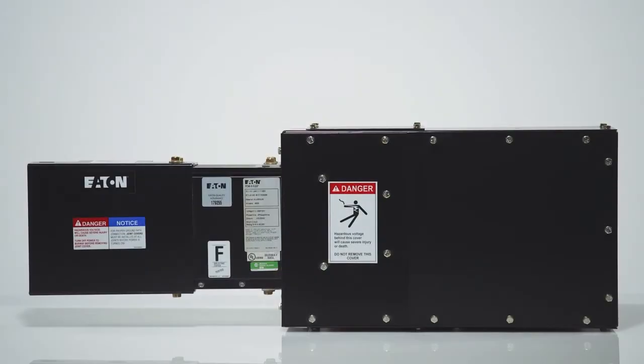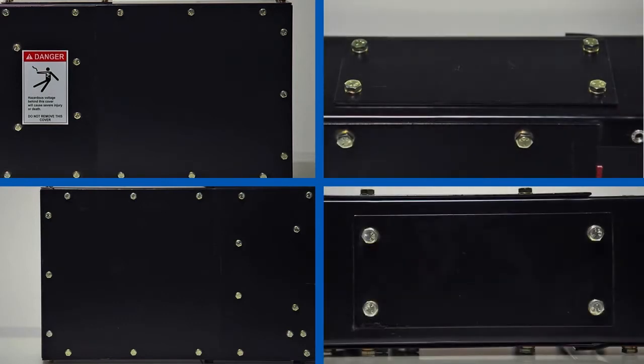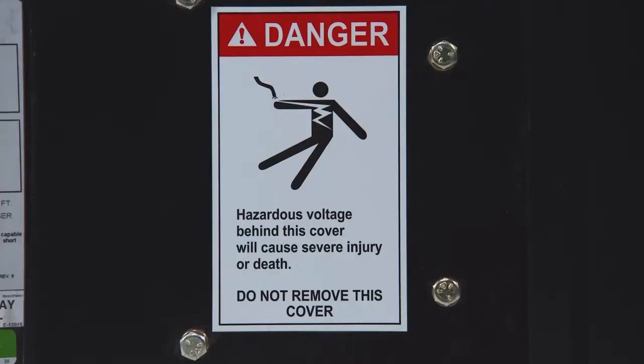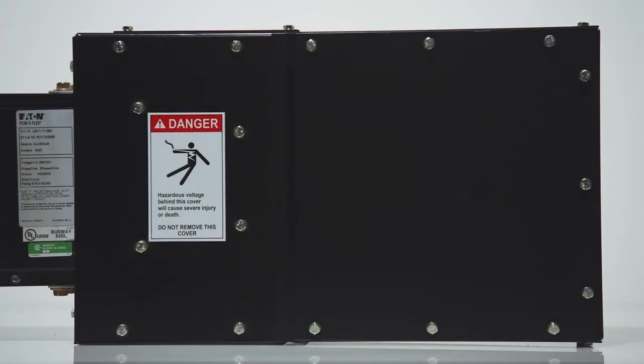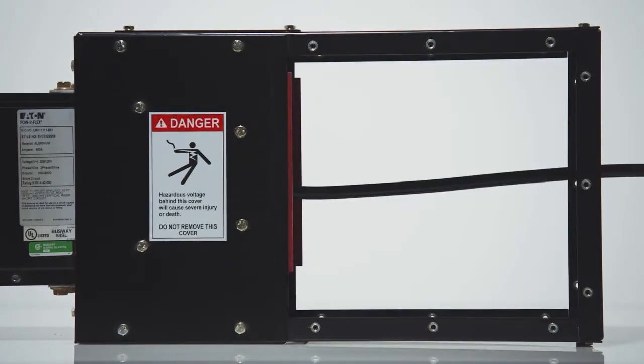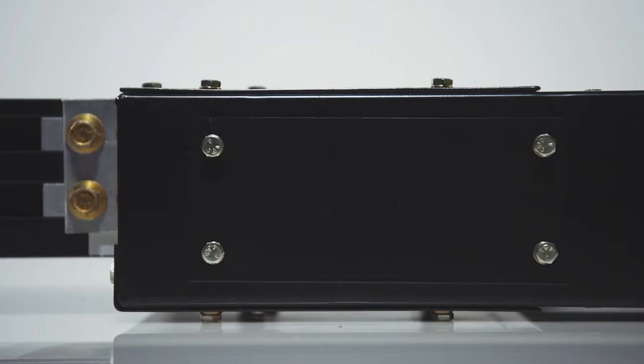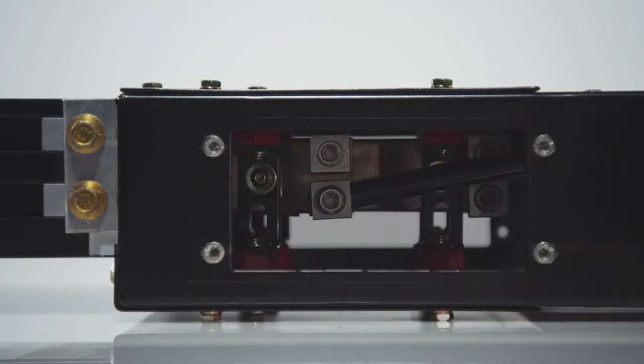When power is fed to the busway via cable and conduit, an end cable tap box is used. End cable tap boxes have 4 removable covers: the front and rear covers, and the top and bottom access plates. The covers with the warning labels between the top and bottom access plates should not be removed. To insert the cable into the lugs, remove the front and rear covers. To tighten the mechanical lugs onto the cable, remove the top and bottom access plates.